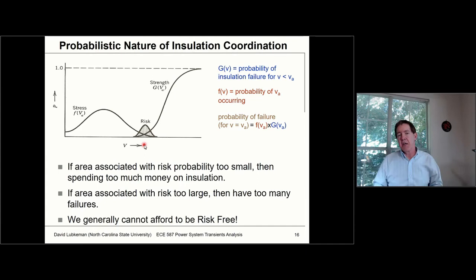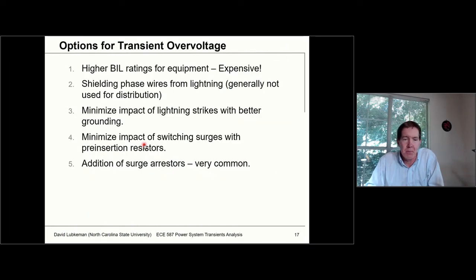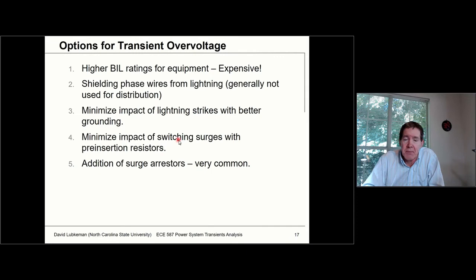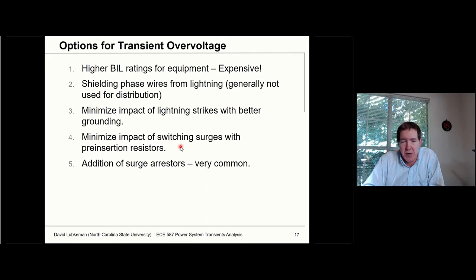As for protection options, you could use higher BIL ratings for equipment — but very expensive. You could put up shielding wires for lightning, though these are generally already there and turn out not to be effective for distribution. You could minimize the impact of lightning strikes by improving grounding — putting more ground stakes in the ground. You could put pre-insertion resistors in circuit breakers for energizing lines to minimize that impact. And then the next thing we're going to talk about is the addition of surge arrestors.